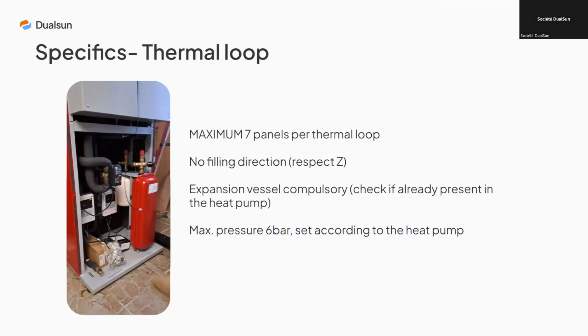Also, this slide, and finally, there are a few things to bear in mind when sizing and installing your systems. First, we impose a maximum of 7 panels per thermal loop. If more, you need to do at least 2 thermal lines and install these 2 thermal lines ensuring hydraulic balancing, either by means of a Tichelmann loop, if 2 lines are equal, or 3 or more lines are equal, or by installing balancing valves. I'll show you just after.